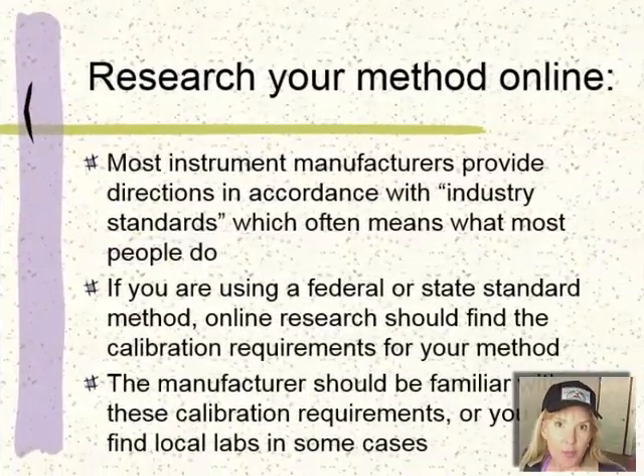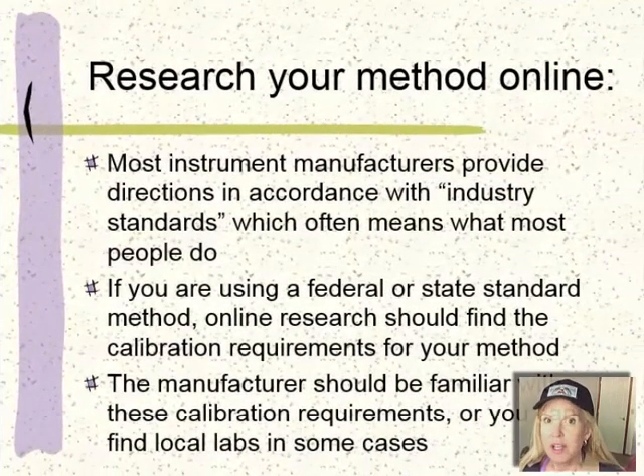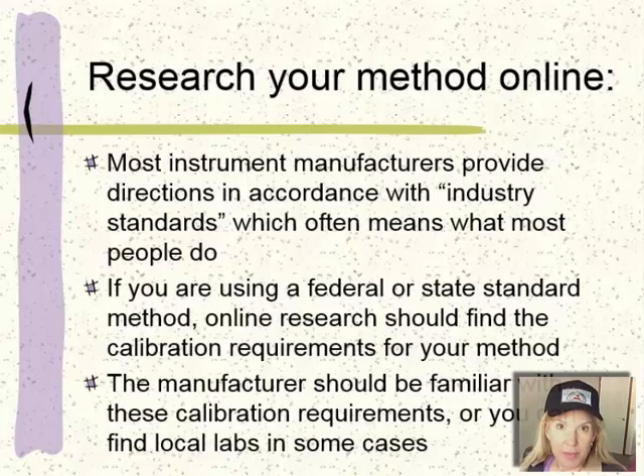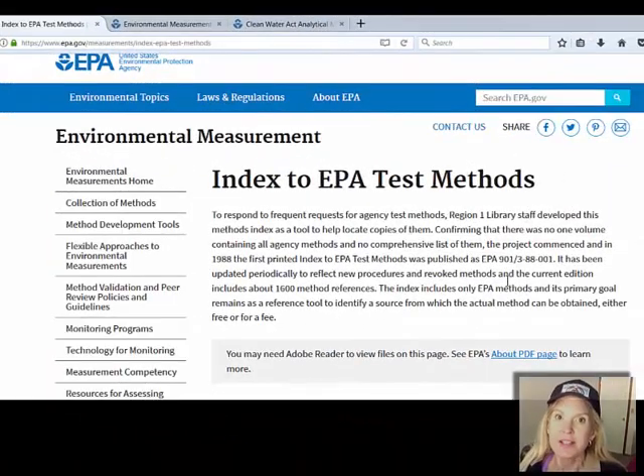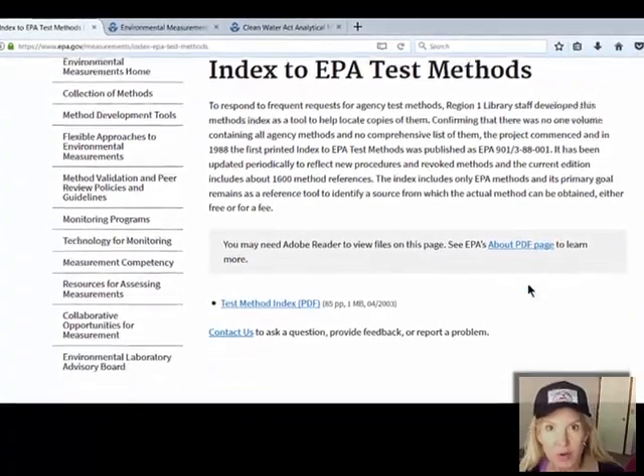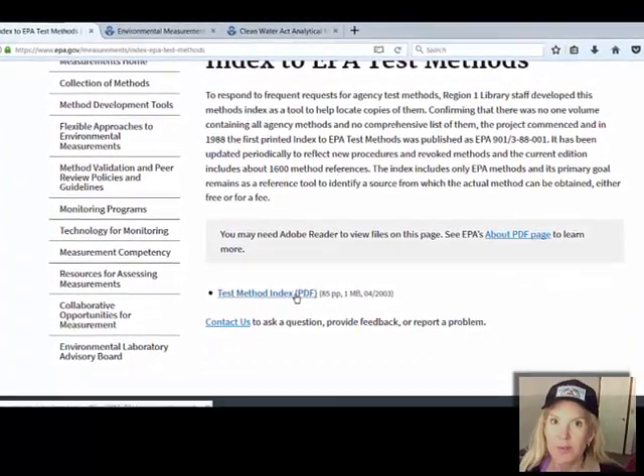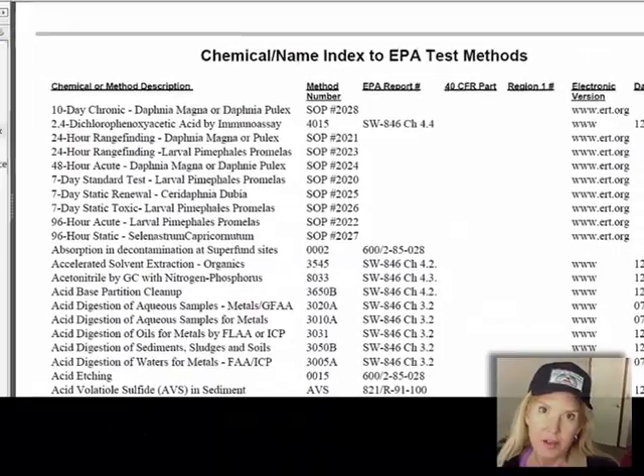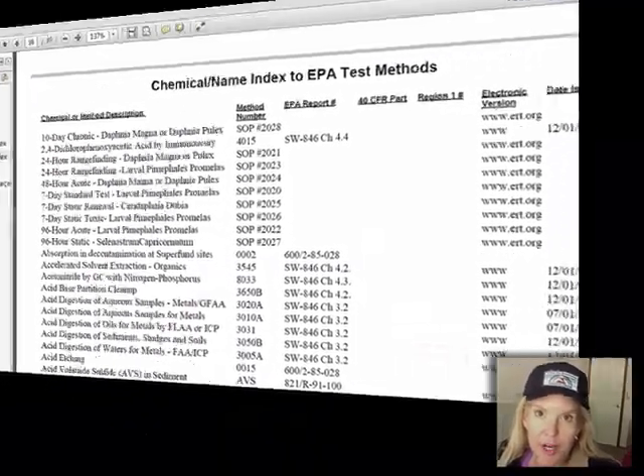But of course, if you're making measurements to determine if some parameter in your environment meets a standard, then usually that standard will have associated documentation for the requirements for QA. Sometimes that doesn't exist, and then you need to research how well most instruments do and try to meet the requirements that are usually expected for measuring that parameter.